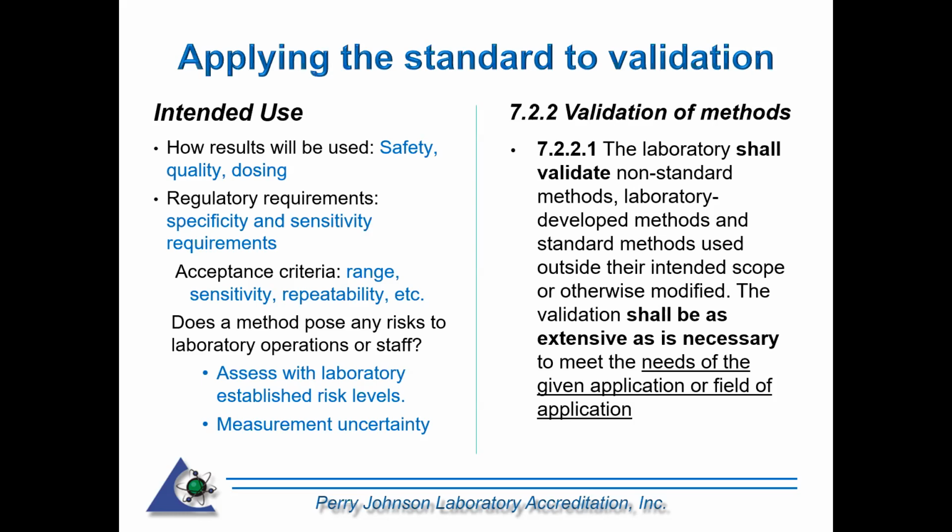Okay, so everything on the intended use side, we have looked at it previously, but now let's look at it in the context of the standard itself. So in the clause that the laboratory shall validate non-standard methods, laboratory developed methods, and standard methods used outside their intended scope or otherwise modified, and that the validation will be as extensive as is necessary to meet the needs of the given application or field of application. What that means is you have set your acceptance criteria, and so the validation should be extensive enough to demonstrate that all of those parameters have been met.